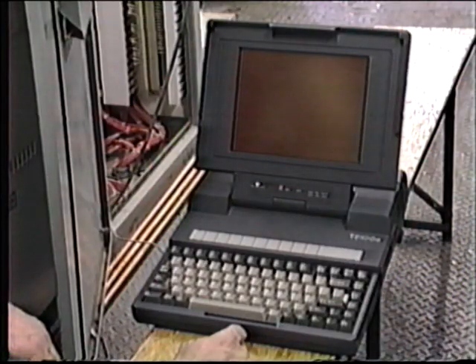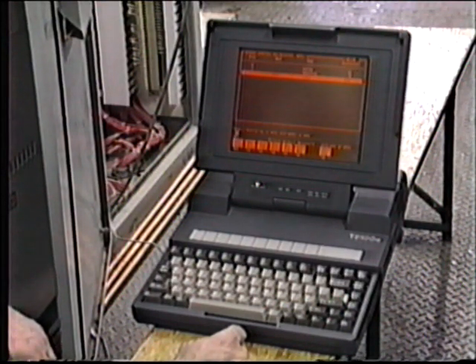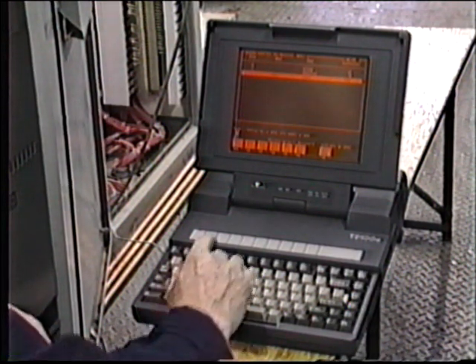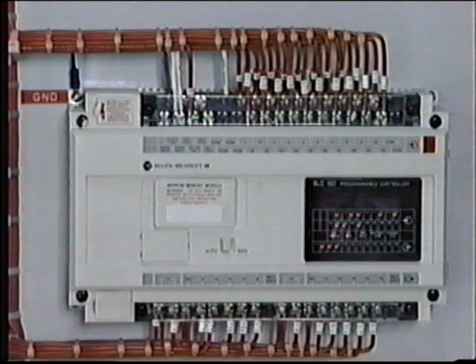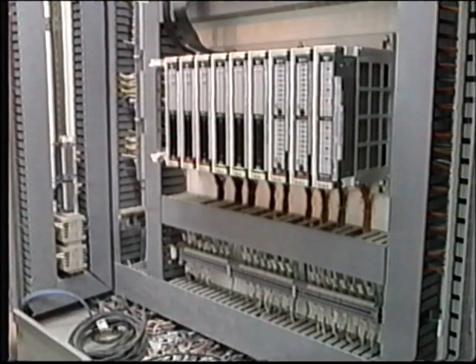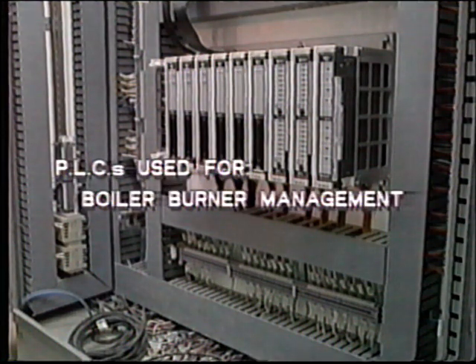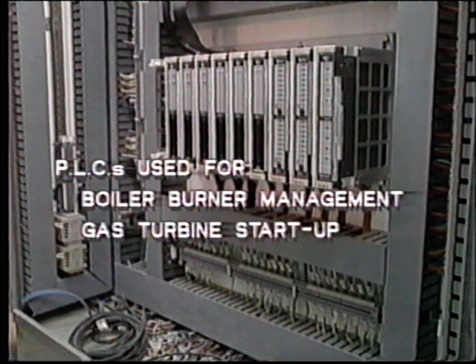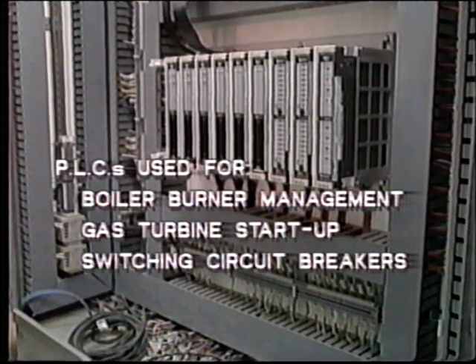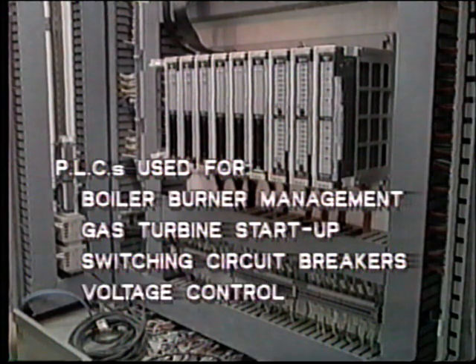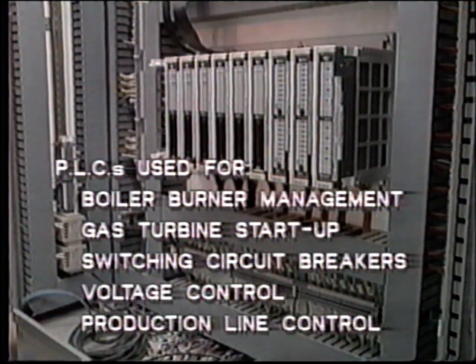In the case of the PLC, the process logic is contained in the software. Thus, if a process change is required, it is simply a matter of rewriting the software program. In fact, a typical compact PLC can be moved from one location to another and programmed to perform a totally different task. You will find the same standard PLCs used for such widely different jobs as boiler burner management in the power station, automatic gas turbine startup, automatic switching of circuit breakers, voltage control, and production line control in a factory. It is the programmable logic feature which makes this type of controller so useful.